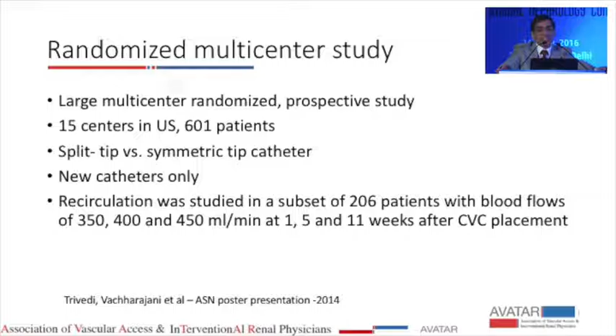Similarly, when they connected the split tip catheter in a reverse direction, as you can see, the venous end is being used as the arterial pull, so there is a high chance of increasing the recirculation. As opposed to that, the symmetric tip, in reversed or in standard connection, did not interfere with the recirculation, because as you can see, the dye is way away from where the venous and the arterial channels are, even after they are reversed.